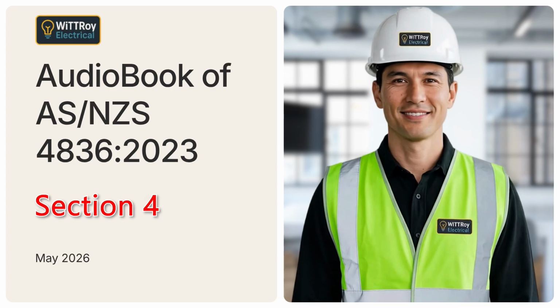Clause 4.2, Safety Observer. Clause 4.2 explains when a safety observer is required. If the risk assessment shows that a safety observer is required, then the work must not be carried out without one. A safety observer has a very serious role. They must watch the work, warn the worker about danger, and stop the work if needed. For example, they may warn the worker about accidental contact with energized electrical circuits or equipment. They must not do another task that distracts them from observing the work. They must be able to communicate quickly and clearly with the person doing the work.